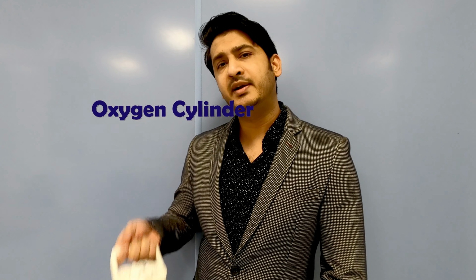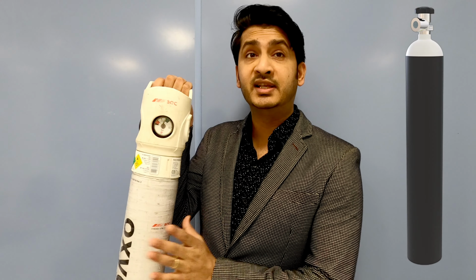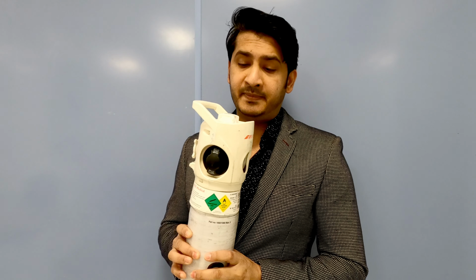Next comes the oxygen cylinder. Each bedside has a portable oxygen cylinder which is used to transfer the patient, and also acts as a standby in case of any central oxygen failure. When we check this, we have to make sure the level of oxygen is always more than half, and if it's low, change the cylinder immediately.